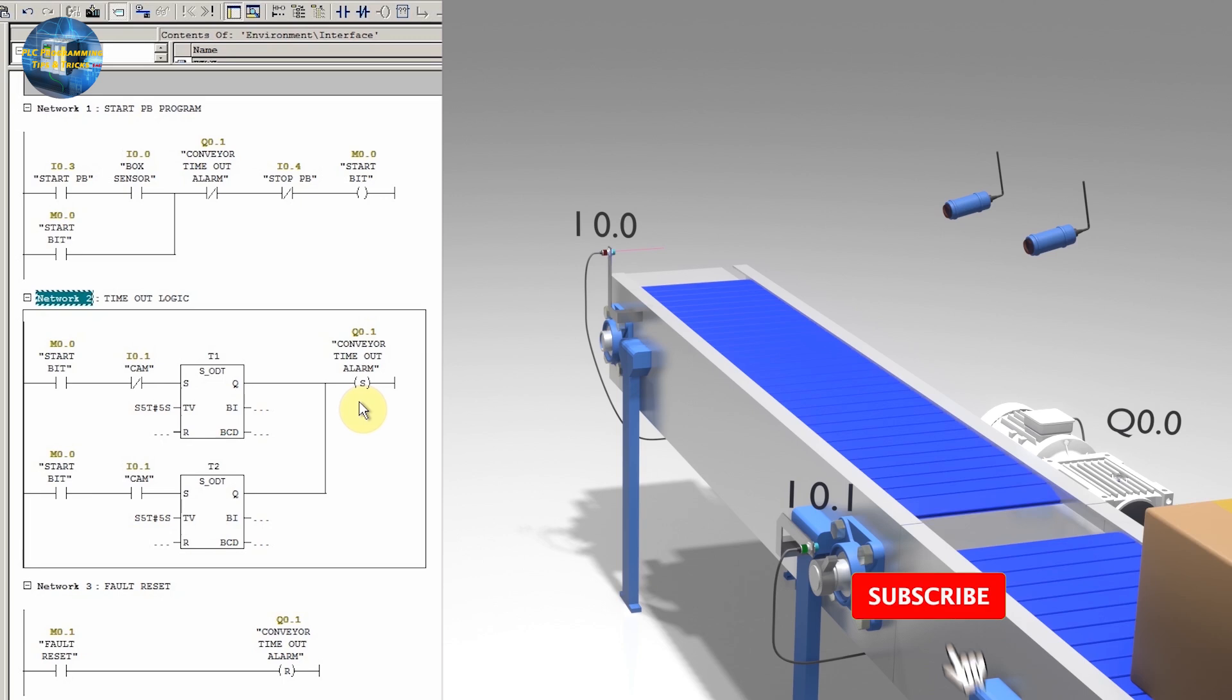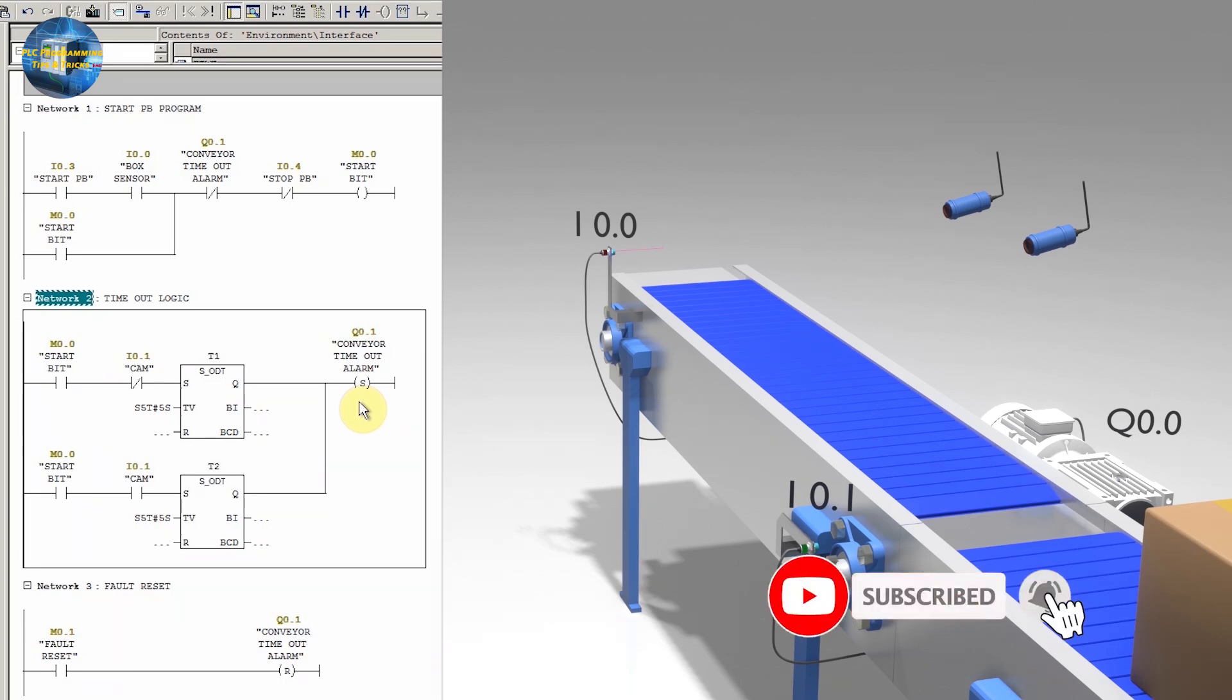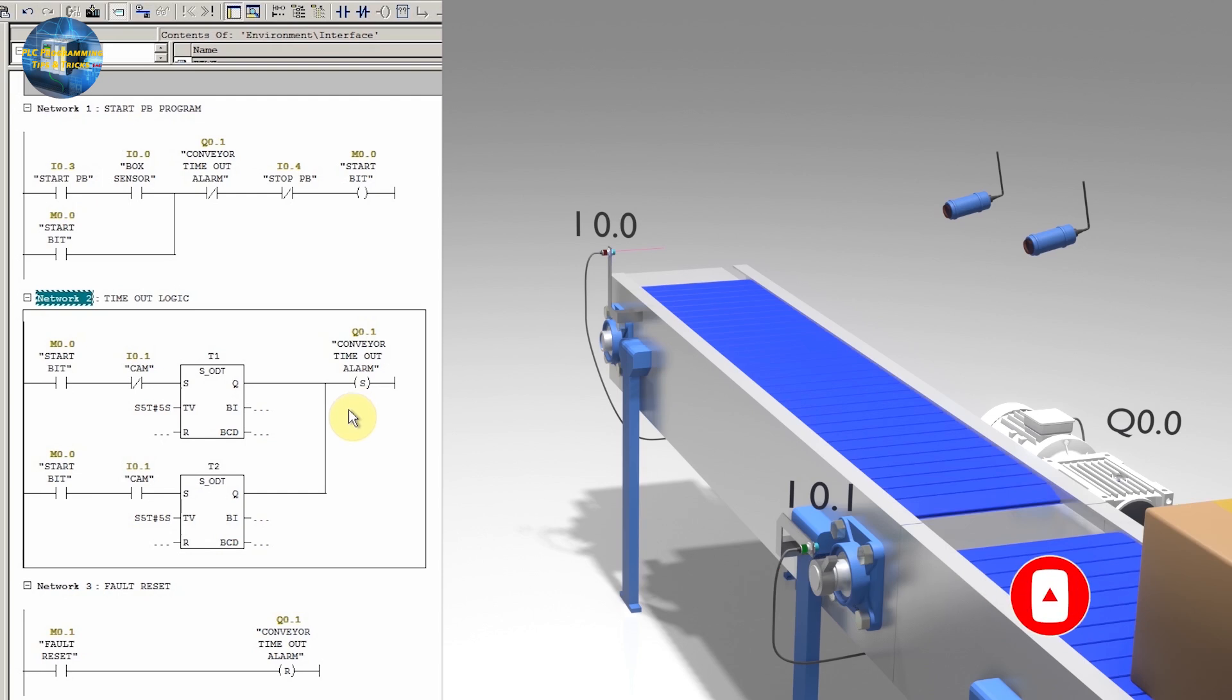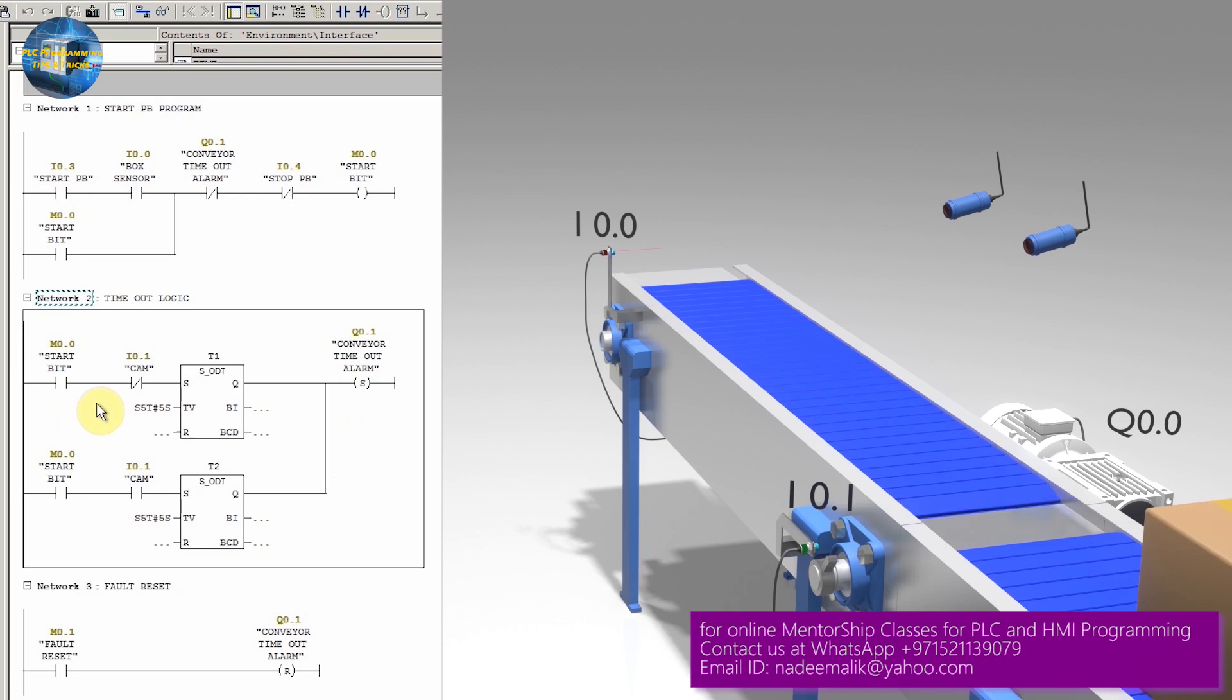Condition number two is that if the conveyor belt malfunctions and cam is in front of the sensor I0.1, this time the timer T2 will get activated and after 5 seconds it will activate the timeout alarm. Next we will download the program into the PLC and monitor it.